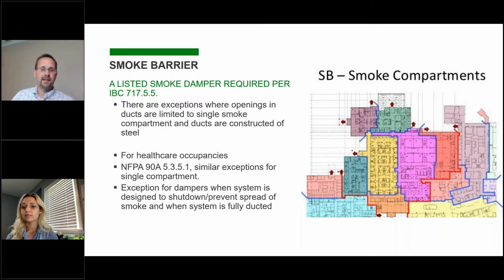Another thing is in the IMC, it refers to this section as corridor smoke barriers. And one important thing to note on that is the corridors referred to in there are egress corridors that are required to be fire rated by the code. So just because you have something that's labeled as a corridor on the plan doesn't mean you need smoke dampers every time you serve it.